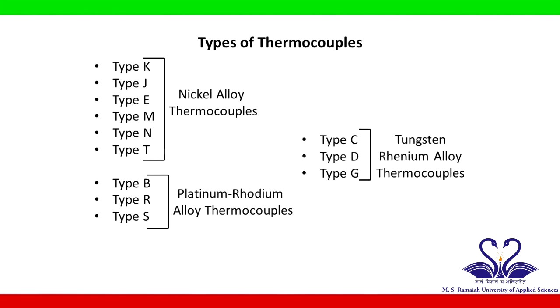Thermocouples are categorized into three main categories: nickel alloy thermocouples, platinum rhodium alloy thermocouples, and tungsten rhenium alloy thermocouples. The thermocouple types K, J, E, M, N and T are classified as nickel alloy thermocouples. Types B, R and S are classified as platinum rhodium alloy thermocouples. Types C, D and G are classified under tungsten rhenium alloy thermocouples. Any other type of thermocouple one comes across is either a noble metal thermocouple or a different form of the aforementioned thermocouples.